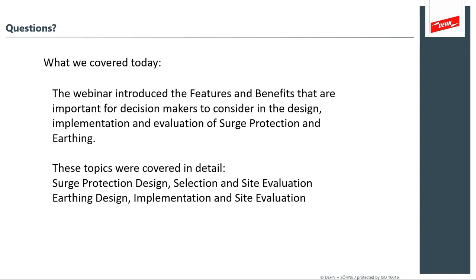Yes. As you mentioned, severed earth connections can lead to instrumentation problems. What kind of problems are we talking about? Well, the severed earth connection basically means that you're going to have unequal potential. So if there's a ground potential rise, you'll have the instrument experience a different potential than the controller. And now when there's a change in voltage, there's going to be a current flowing, and the current will flow on your control wires, and it'll then punch through and find a path. And that's the whole point about equipotential bonding. You want everything on the same essential voltage and not force it to find a path through your instrument. And if it's a high enough surge, it will find a path.